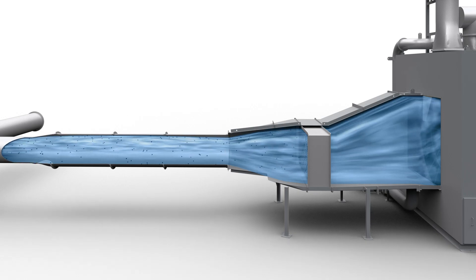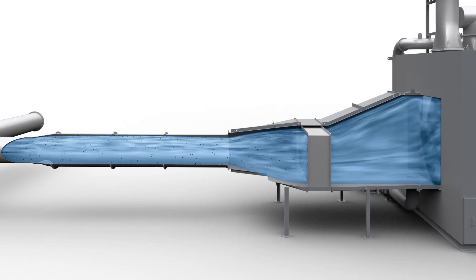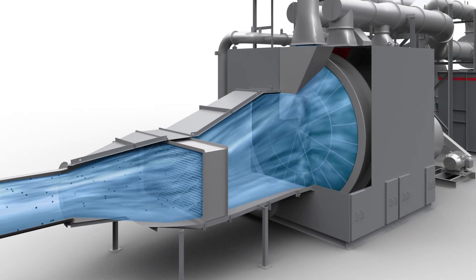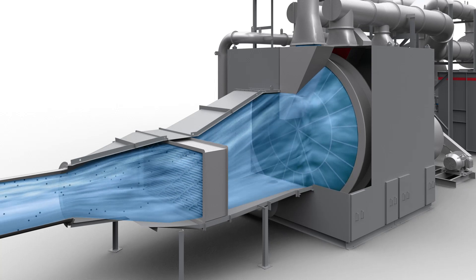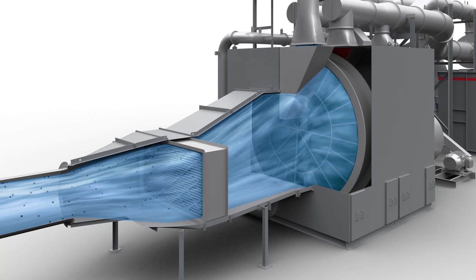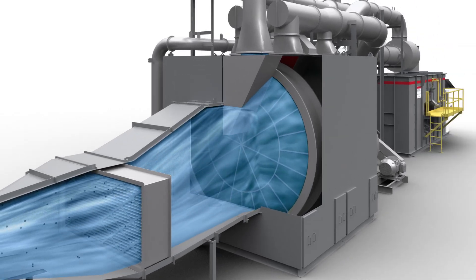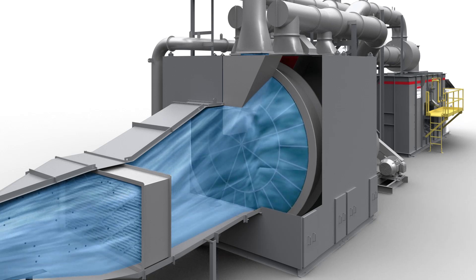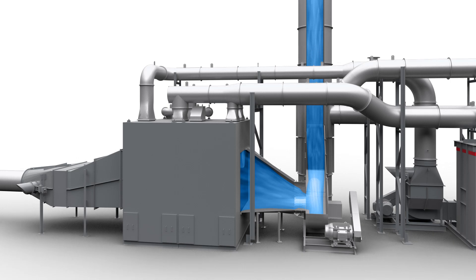The polluted airstream first passes through a filter box to protect the concentrator from any particulate that may come from the process. It then passes through a rotor concentrator wheel where volatile organic compounds are separated from the air through adsorption onto the media.